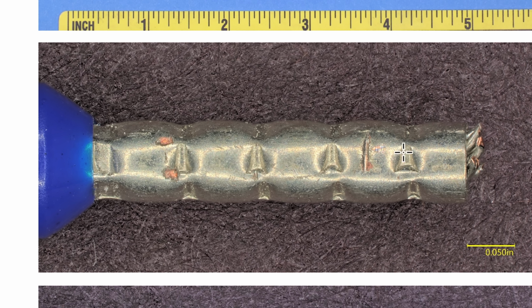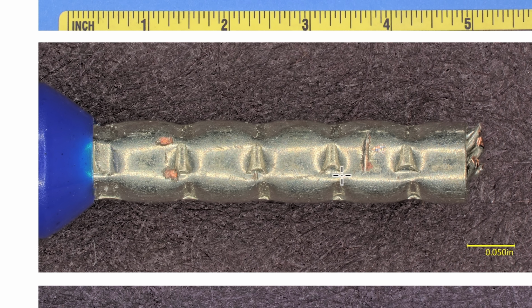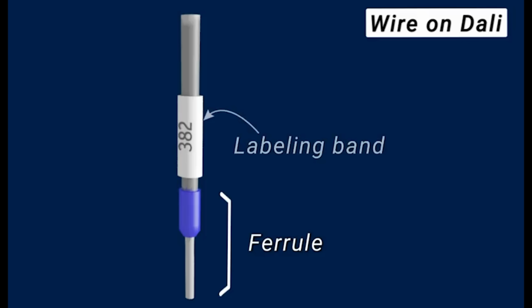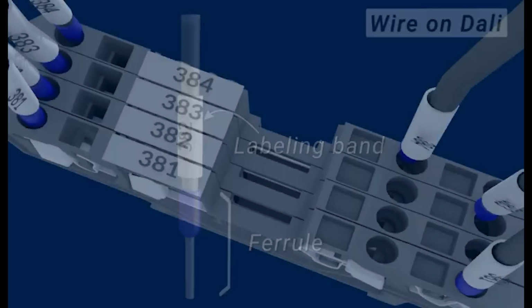And what a metal ferrule is, it's basically a metal tube that surrounds your stranded wires that are all twisted up inside there, because it's a lot easier to stick a solid metal tube into the connection point on your terminal block than it is to try to insert these twisted wires here. And then you can see 1, 2, 3, 4, 5 points on here where the ferrule is crimped onto your wires. Okay, and each wire and ferrule has its own labeling band, as you can see here in the diagram.